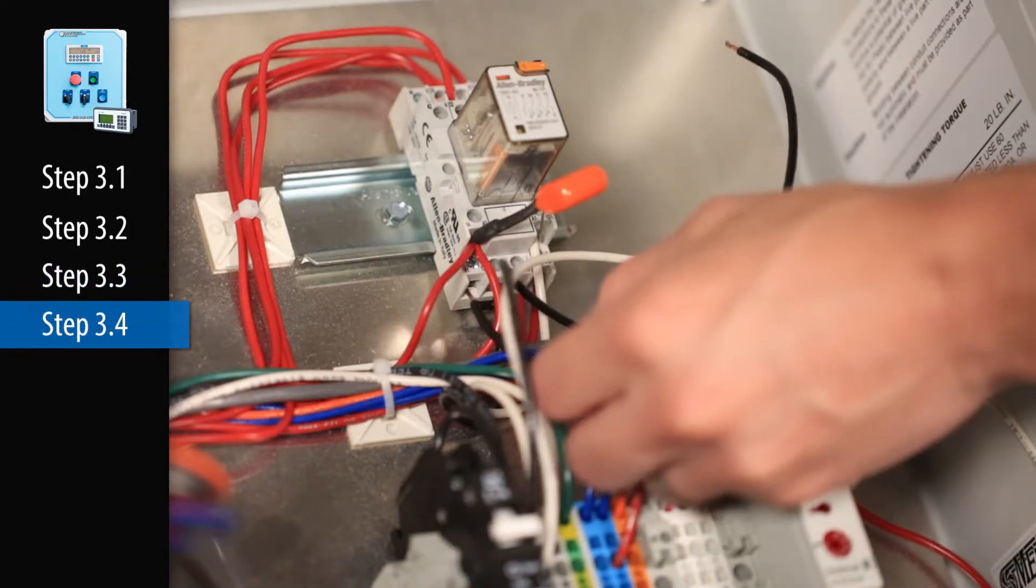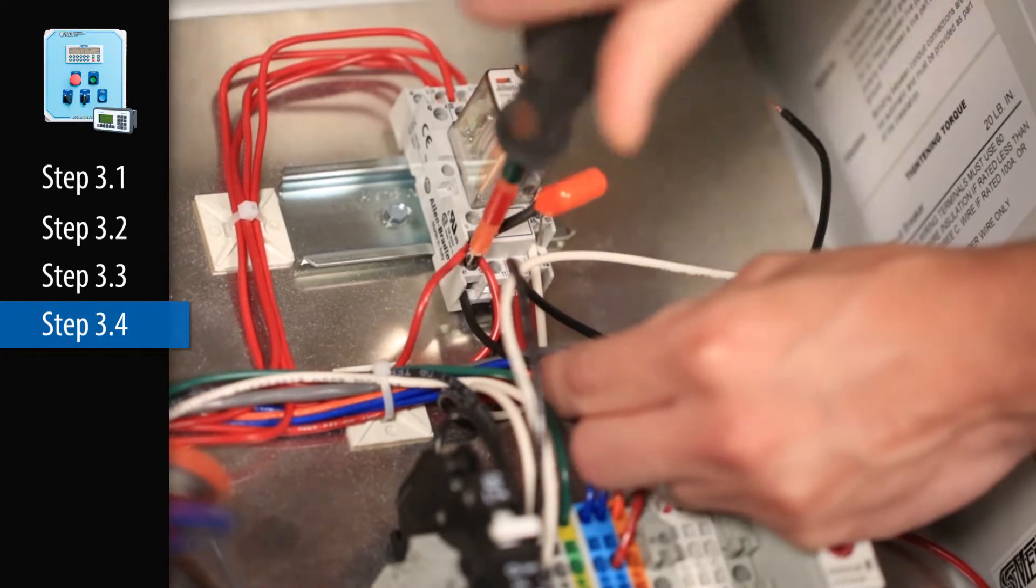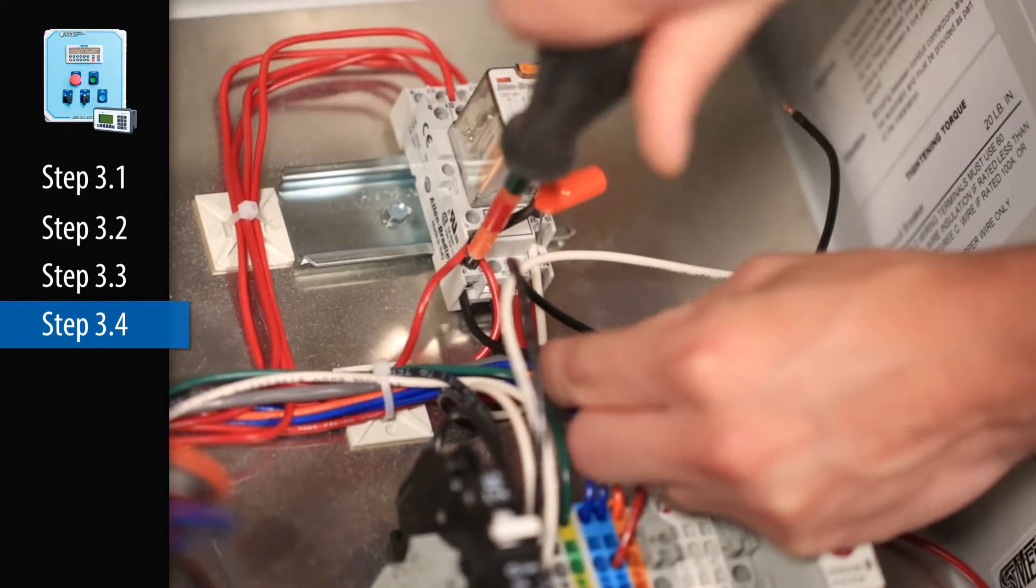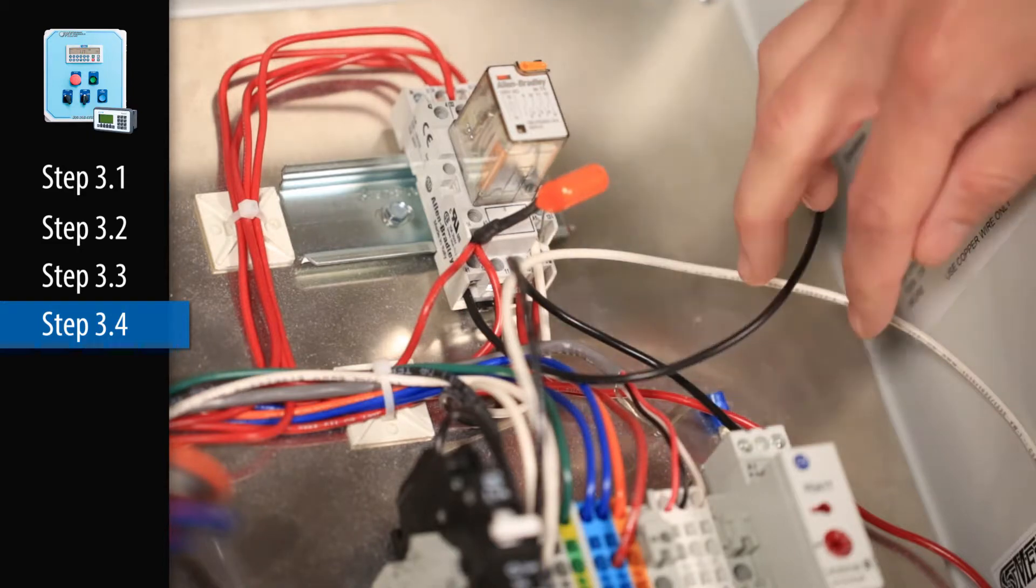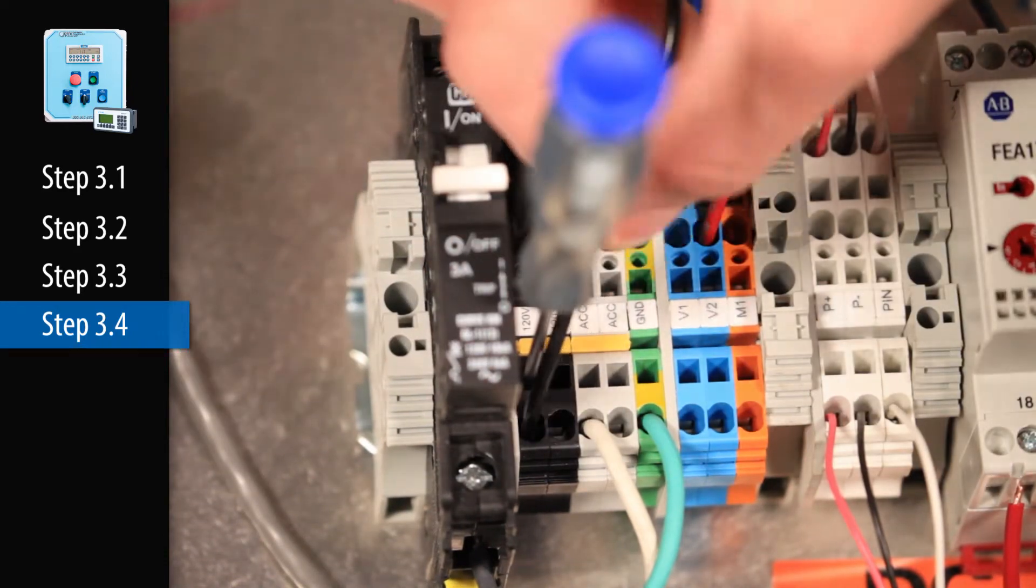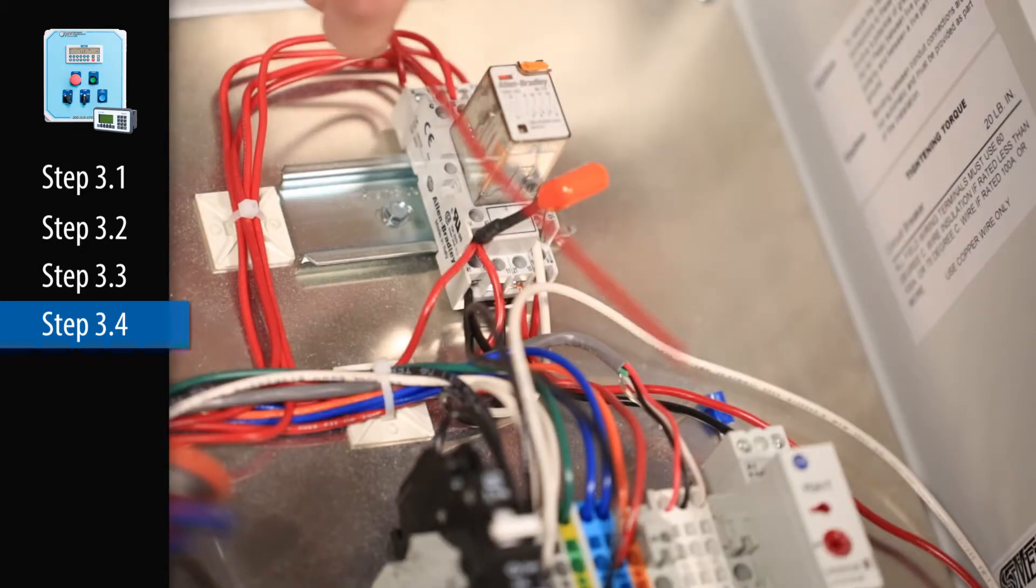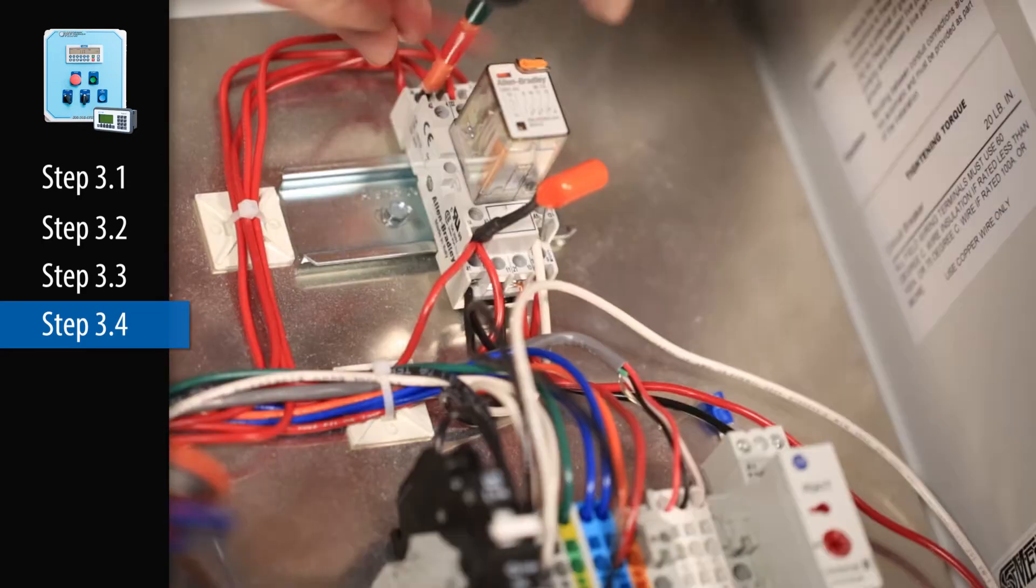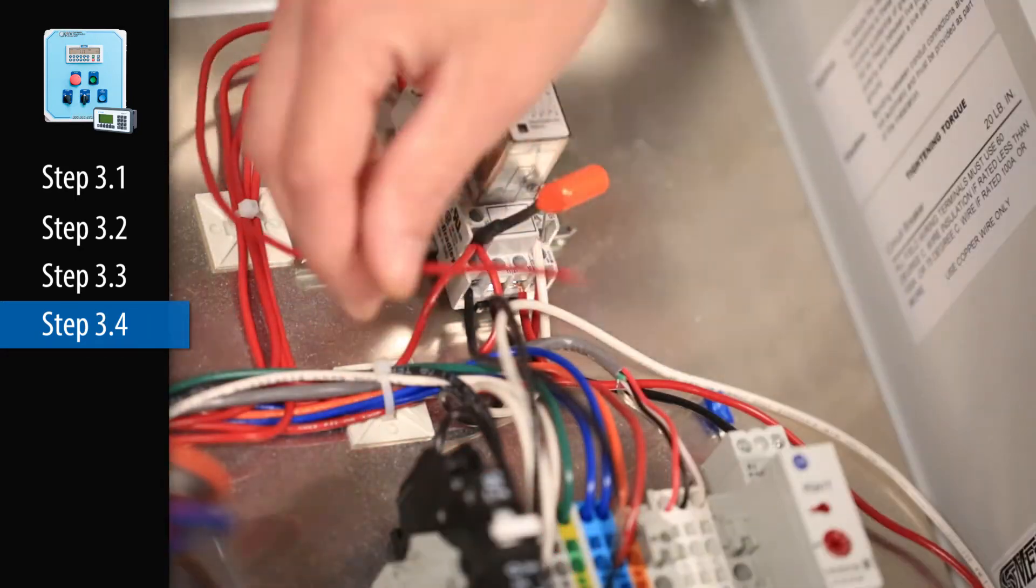Step 3.4. Find the master control cube relay on the back panel. Connect 120 AC power to terminal 12 on the master relay. Run another wire from terminal 8 on the master relay. Connect 120 AC power to terminal A1 on the timer relay.